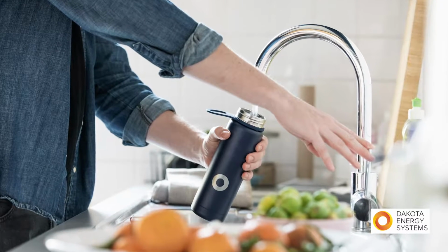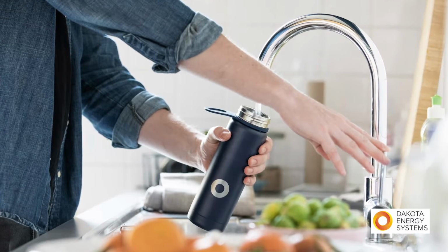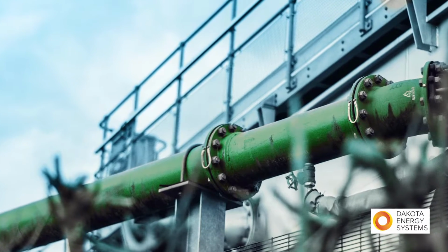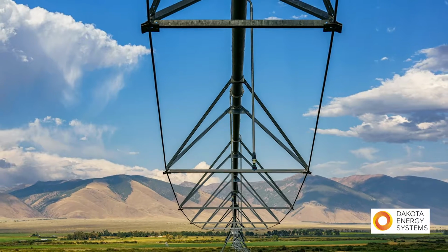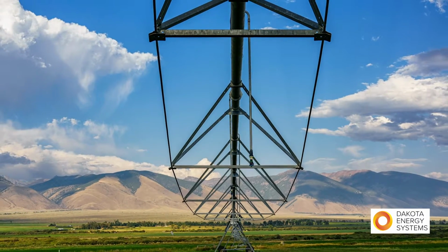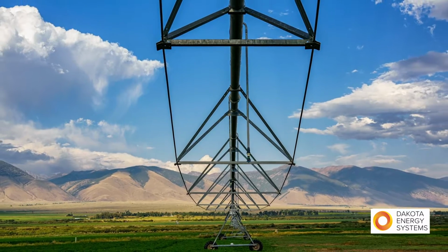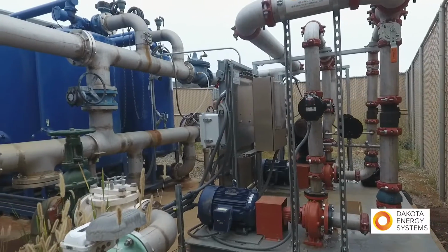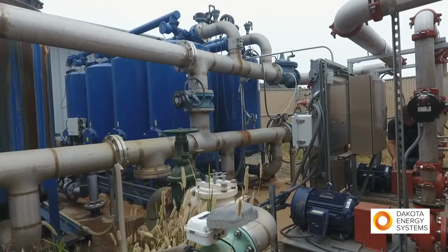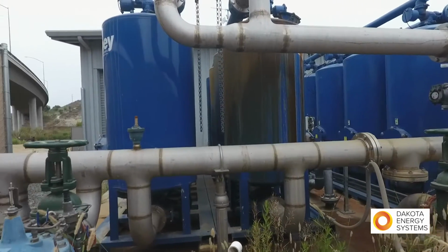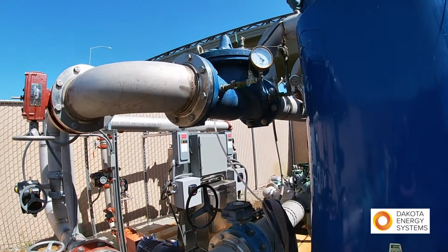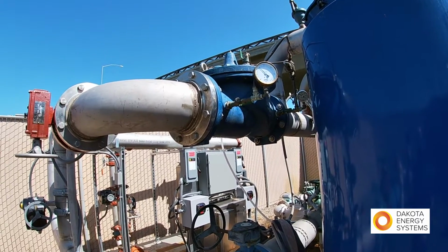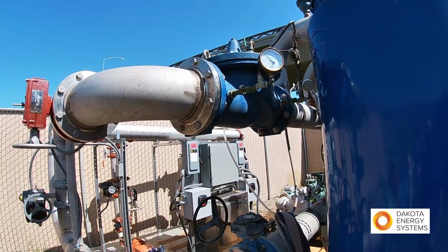Most private and public water districts maintain multiple pressure-reducing stations throughout their domestic potable water system to deliver household and agricultural water at a safe and reasonable pressure. These pressure-reducing valves, or PRVs, reduce the water pressure by absorbing the water flow enough to bring it down to usable pounds per square inch, or PSI.